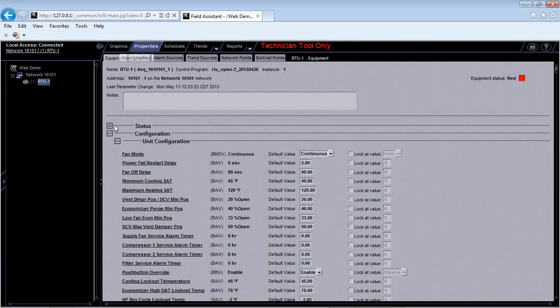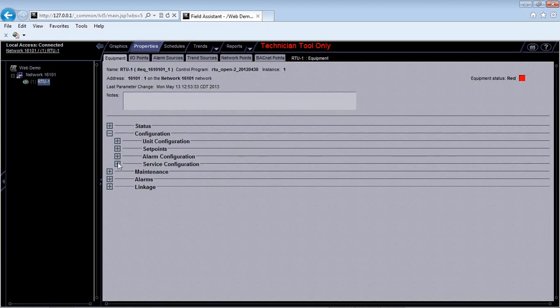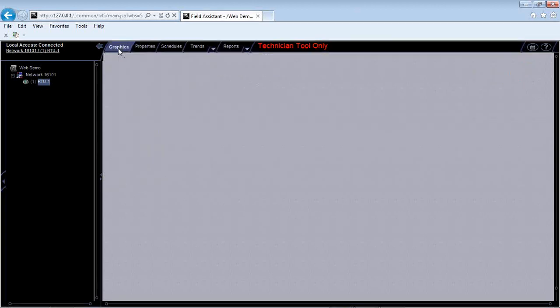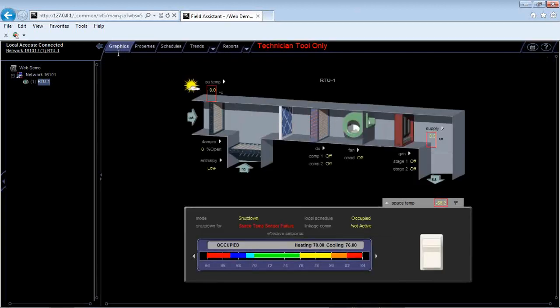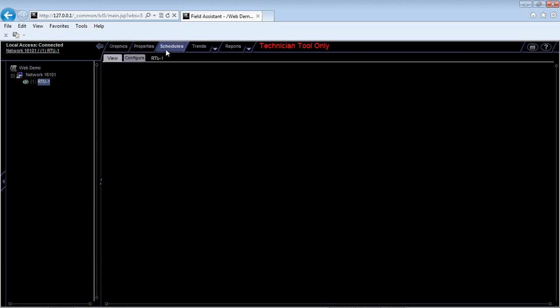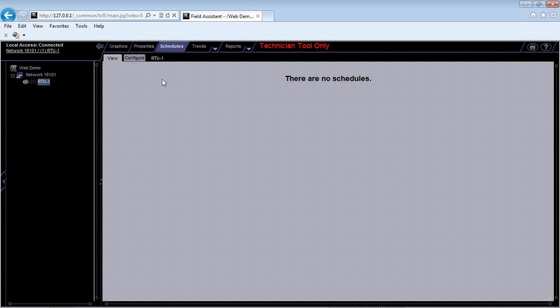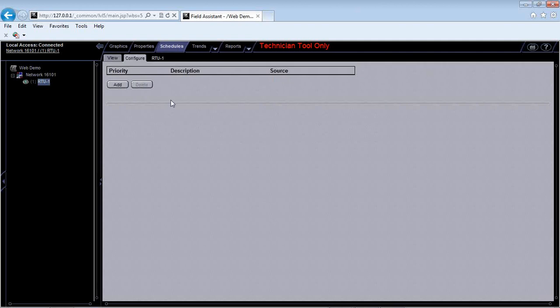So other than that, that's basically the best way to get the unit started and configured so that it knows what you have here. What I want to do is, because I put it into Bacnet Schedule mode, I want to go to the Schedules tab and put a schedule on here. Okay. Right now you'll see there are no schedules. If I go to Configure, I want to add a schedule. This is only local to this controller, but I can add a schedule. You can do multiple types of schedules, right? You can do a normal schedule, which tells the unit go occupied from this time to this time.